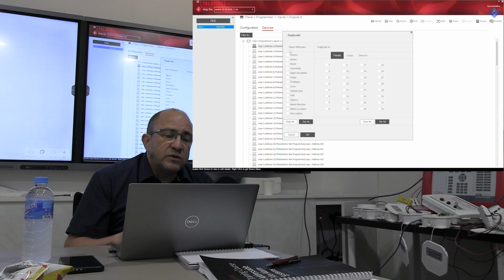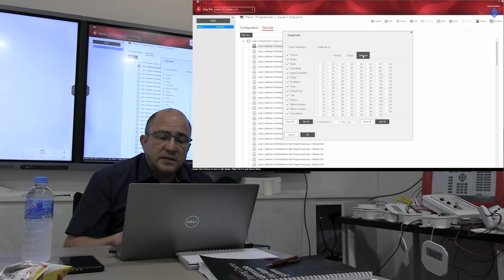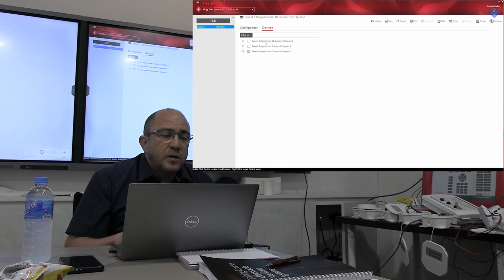I'll select all of these. I would like to copy the device, the active, the mode, the sensitivity, the night set. I would like to copy everything to panel number 1, to loop number 1, and devices I can do this way: 1, 2, 3, 4, 5, 6, 7, 8, 9, and 10. Okay. Programmed 10, inputs 10.